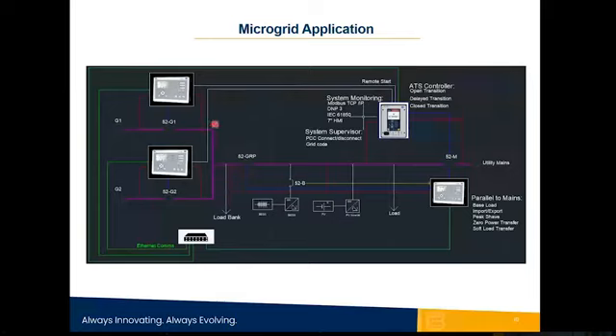But then the system is a bit more complex than just two generators and island load share. Here we have a tiebreaker, and downstream from that tiebreaker, we have a BESS system, our battery energy storage system. It's generating DC, and we convert that to AC. This breaker can close the battery system onto the bus. And then there's a PV array that, same thing, is generating DC and being inverted to AC, and that comes onto the bus as well.